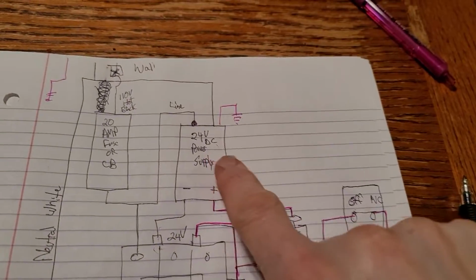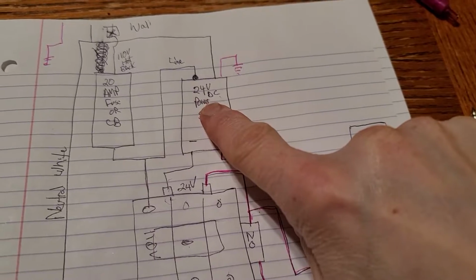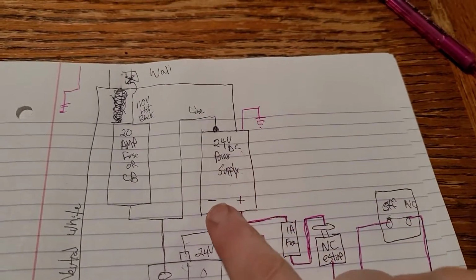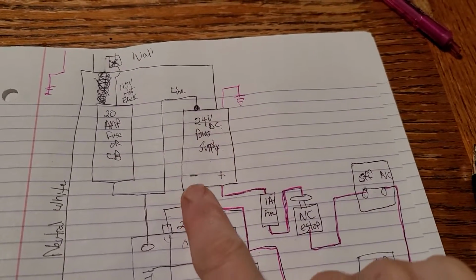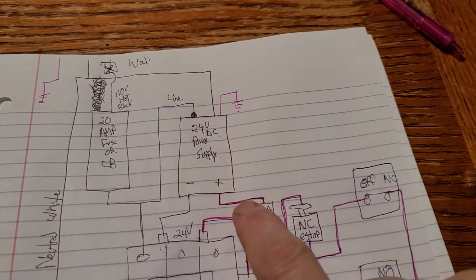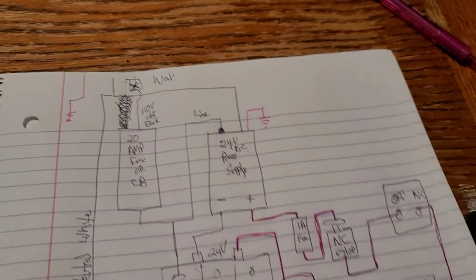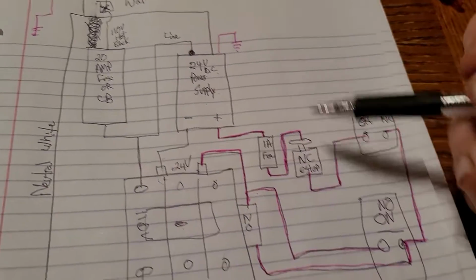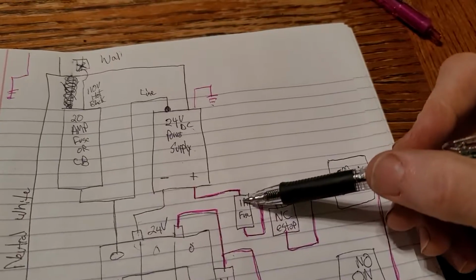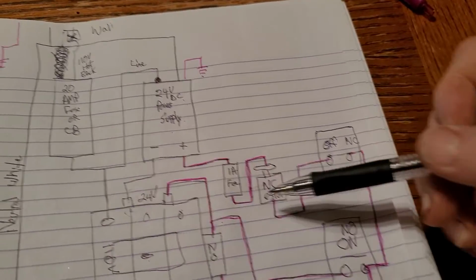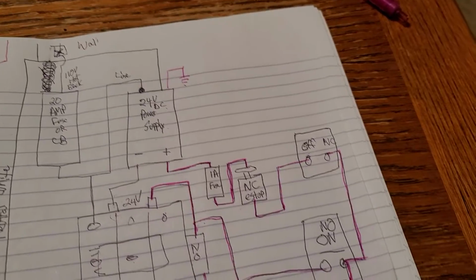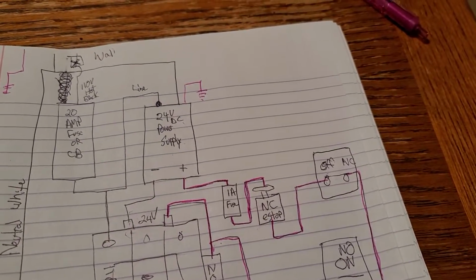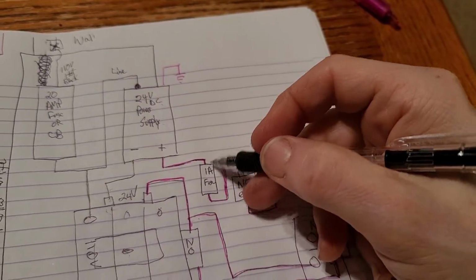Right? So we now have power here to the 24 volt power supply. Now we've got the common. This is 24 volt common and 24 volt positive. We're going to take that 24 volt positive, I drew it in red. And the first thing you do is you're going to run it through that 1 amp fuse. So if something were to happen, let's say you were to short out and short yourself, that 1 amp fuse is a quick blow. It's going to go right away. That's what makes it safe.